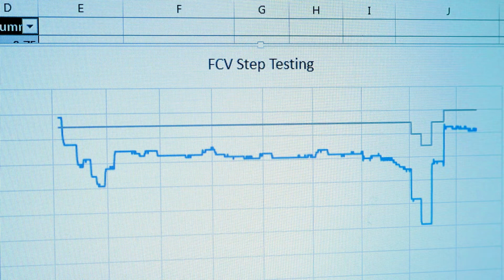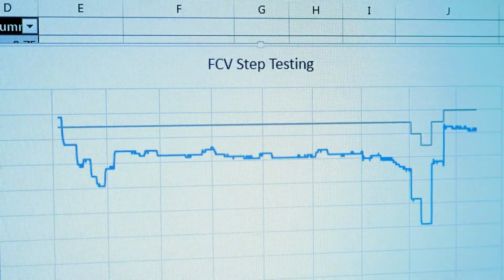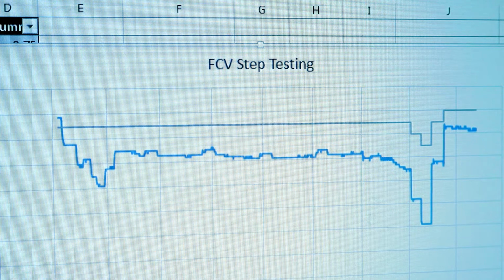We can also see in the trends the delay between the input change and the output change, and also calculate the time constant based on the first order lag transfer functions. These parameters will help us automate the Big Red Skid.